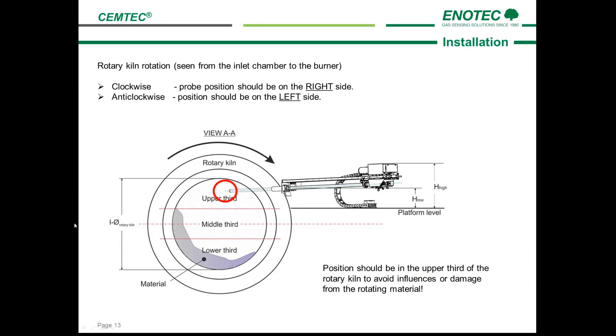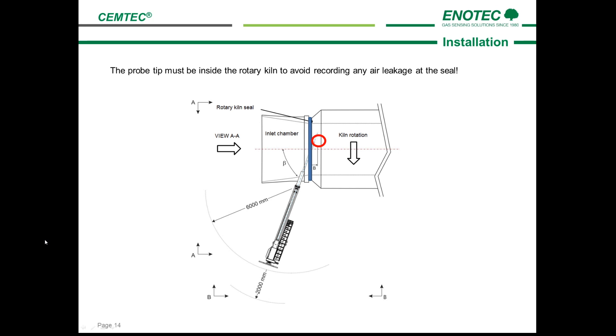The best sampling technology won't help achieve the desired results if the probe is not installed in the right position. As you can see in this drawing, the kiln rotates clockwise when seen from the inlet chamber to the burner — in this case the probe needs to be installed on the right side. If it were to rotate anti-clockwise, we would recommend an installation on the left. Furthermore, the probe must be positioned in the upper third of the kiln in order to avoid influences or damage from the rotating material. It's also extremely important that the probe tip is inside the rotary kiln after the kiln seal, otherwise false air will be measured.